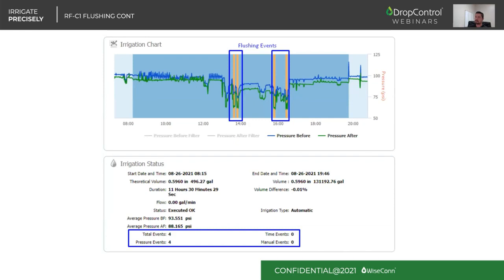Also, under the web browser visualization, under each irrigation event, you are going to be able to see the different sensors associated. So in this case, these blue and green lines are making reference to our pressure before the filter and our pressure after the filter. And the orange background color is making reference to the different flushing events. So we do know that during this irrigation, we had a total of 4 different events, and also we can see the behavior of the pressure transducers or the pressure readings throughout these events, how the difference between the pressure before and after got higher, which triggered the flushing, and how they got normalized after the flushing. And finally, as a summary, we do have the total amount of events during this irrigation and what triggered them. In this case, we got a total of 4 flushing cycles, and all of them were triggered by pressure or pressure differential.